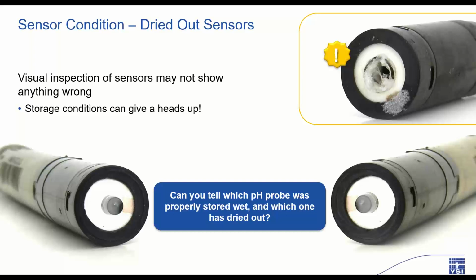These other two pH electrodes look very much the same. It's tough to tell sometimes if the pH sensor was stored properly. The clue lies in the way the pH probe was found. Was the bottle that the sensor was stored in dry? If the sensors were stored on the sonde with some water in the bottom of the calibration cup, did it dry out over the storage period? If you discover at the beginning of the season that your pH sensor and your DO membrane cap were allowed to dry out, this is your first clue that there is work ahead before you will be ready to collect good quality data.